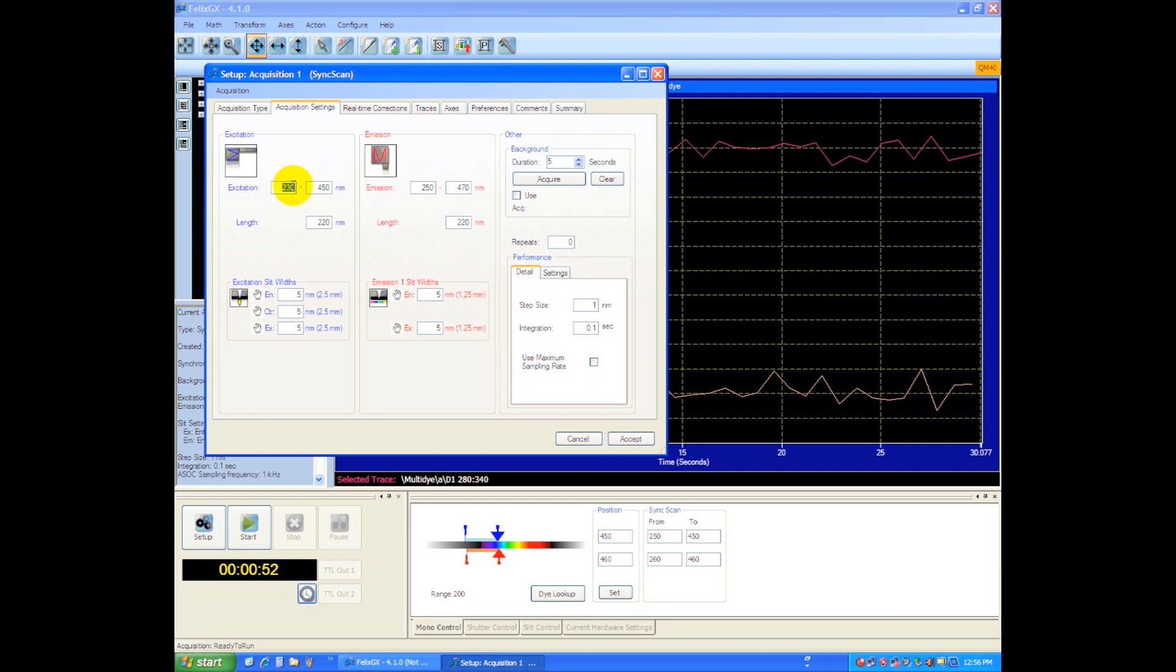So when this mono is exciting at 230 it'll be looking at the emission at 250, so we'll always retain that 20 nanometer shift between the excitation and the emission through the entire scan.